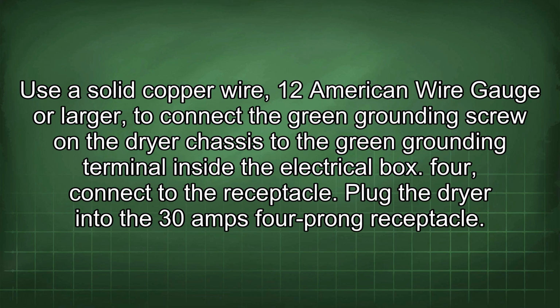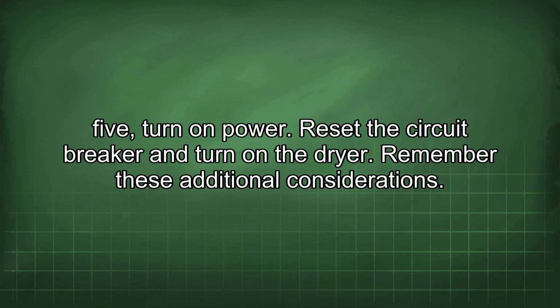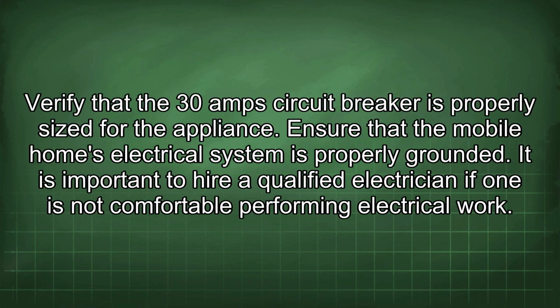4. Connect to the receptacle. Plug the dryer into the 30 amp 4-prong receptacle. 5. Turn on power. Reset the circuit breaker and turn on the dryer. Remember these additional considerations. Verify that the 30 amp circuit breaker is properly sized for the appliance. Ensure that the mobile home's electrical system is properly grounded. It is important to hire a qualified electrician if one is not comfortable performing electrical work.